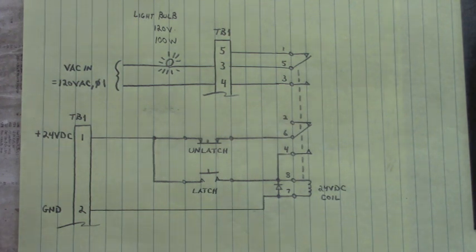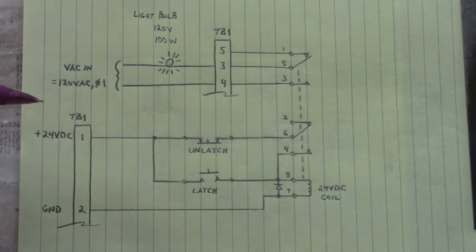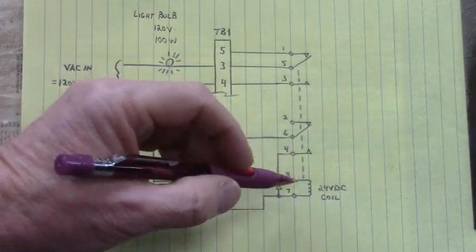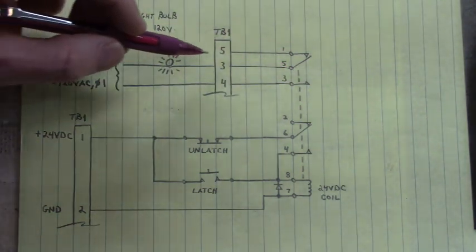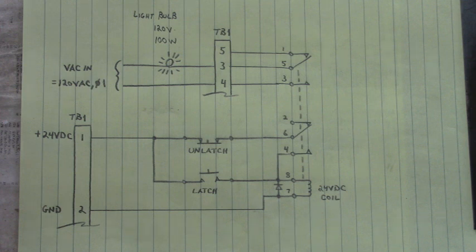Current no longer flows through this contact into that relay coil and it de-energizes and opens those contacts. Now the light bulb, when you push the latch button, current flows through here, energizes the contacts. This one maintains current flow through the coil, and this contact closes, completing the circuit through the light bulb and illuminating that light bulb. Now let's watch the circuit in action.